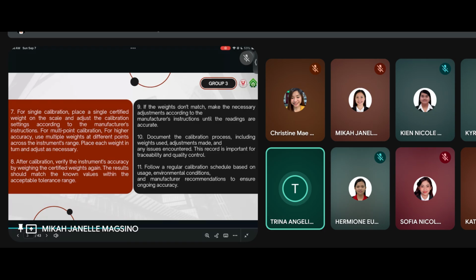Next is for single calibration. Place a single certified weight on the scale and adjust the calibration settings according to the manufacturer's instructions. For multi-point calibration, for higher accuracy, use multiple weights at different points across the instrument's range. Place each weight in turn and adjust as necessary.